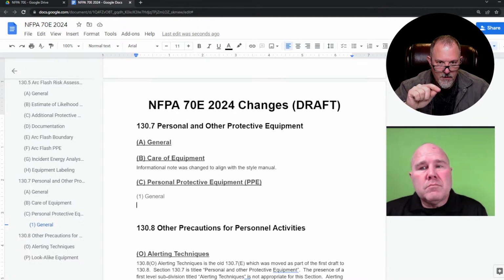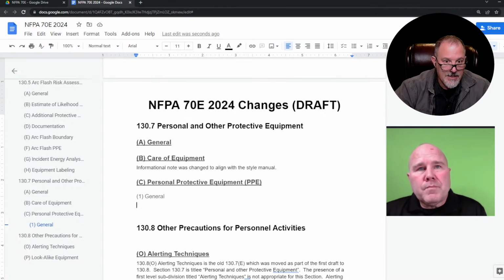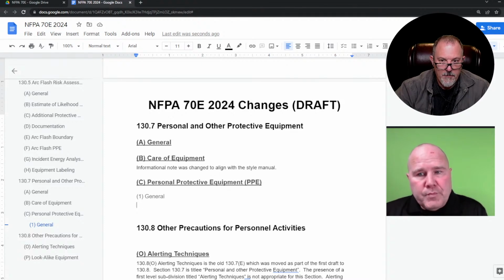The informational note says where the estimated incident energy exposure is greater than the arc rating of commercially available arc rated PPE, then for the purpose of testing for the absence of voltage, the following examples of risk reduction methods could be used to reduce the likelihood of occurrence of an arcing event or the severity of exposure. Item 1 used to say use non-contact test instruments in the equipment. What it now says is use of non-contact capacitive test instruments or a permanently installed metering device in the equipment for indication before using a contact type test instrument to test for the absence of voltage. And they removed the below 1,000 volts.